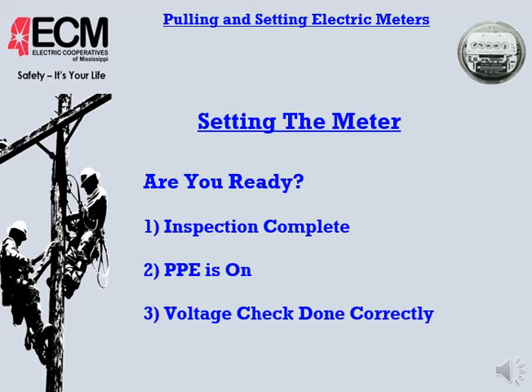Voltage check, is it done correctly? Did we take those 8 steps we talked about when checking voltage to make sure our voltage check was done the way it should be, complete? Have we checked to make sure we don't have a problem anywhere? That voltmeter will tell you if you have a problem if you take those 8 steps and check it the way we talked about.